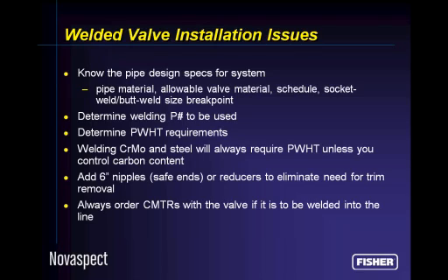So we need to come up with ways to keep you from hurting our valves after you install it, and then you're going to post-weld heat treat it. Know that when you weld chromoly materials into your piping system, that's going to be a P5 weld. You're probably going to have to do post-weld heat treatment unless you control the carbon content, and you need to refer to ANSI B31.1 to know when you can take exception to post-weld heat treatment.